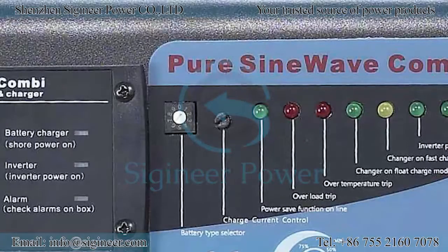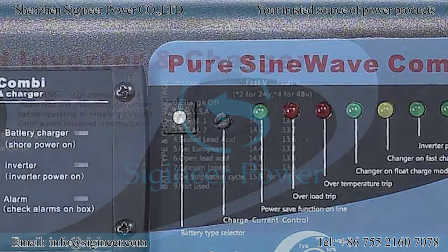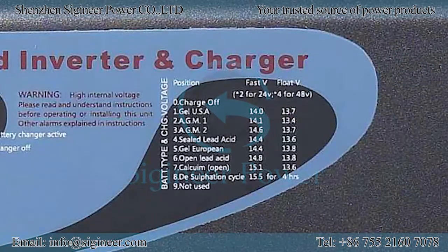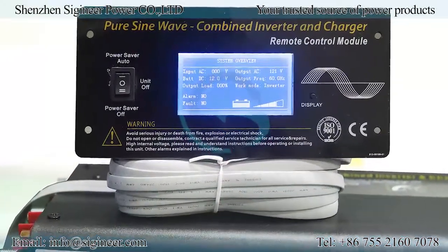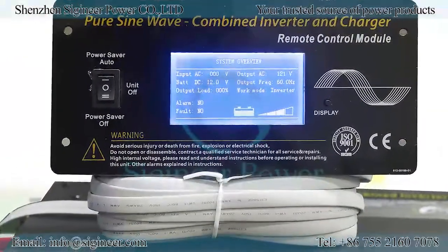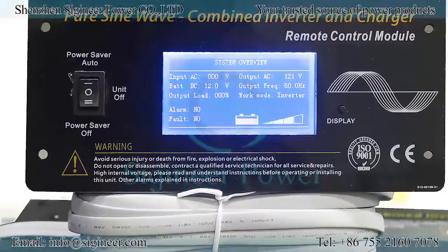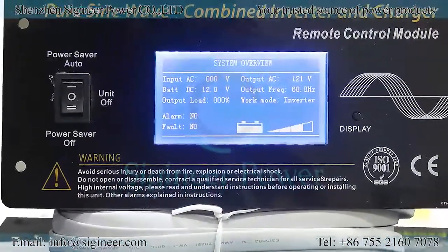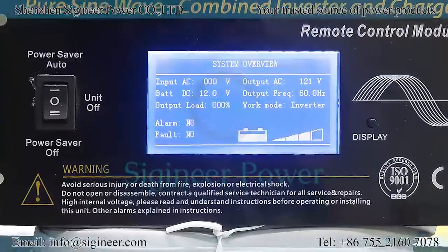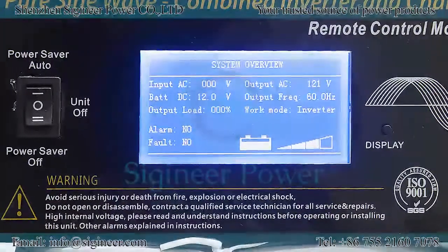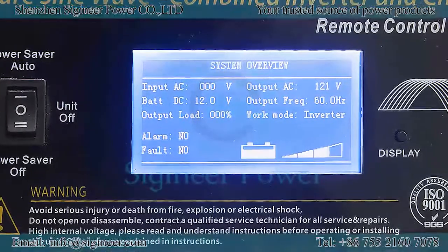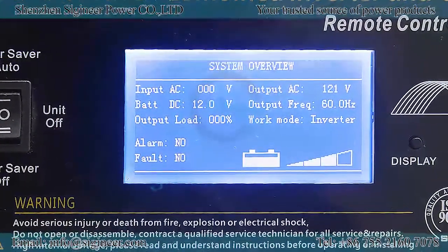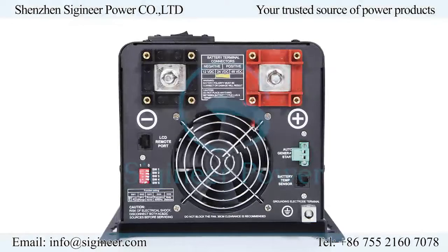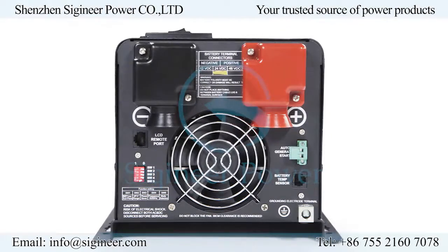The battery type selector allows you to set charging voltages according to the battery type, such as lead acid AGM, GEL, and wet battery. LCD remote panel allows you to monitor in real time the operation of the inverters, such as battery voltage, AC input voltage, AC output voltage, output frequency, load percentage, battery capacity, charger activity, and any alarms and faulty conditions. There are 2 DC terminals, one red, one black.